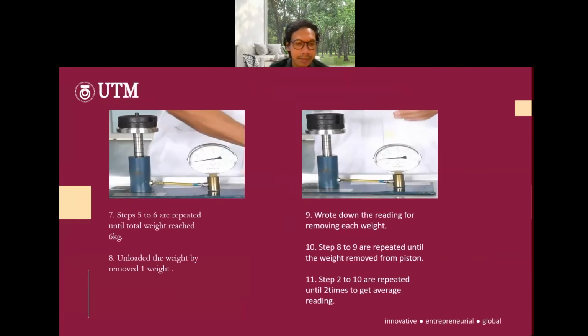Seventh, steps 5 to 6 are repeated until the total weight reaches 6 kilos. Eighth, unload the weight by removing one weight. Ninth, write down the reading for removing each weight. Tenth, steps 8 to 9 are repeated until the weight is removed from the piston. Eleventh, steps 2 to 10 are repeated 2 times to get the average reading.